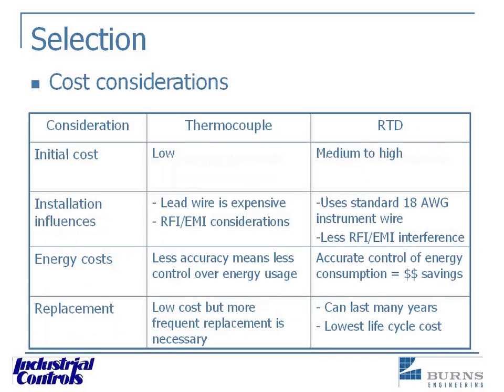Here are some cost considerations. And again, when your temperature demands a thermocouple, all well and good, that's your only choice. But it seems a lot of the time, people will call up and say, look, I just need something down and dirty. I just got to get this thing going. And they opt for a thermocouple when there should be other considerations. People are cutting corners. You're trying to save money. I understand that. But when you take a thermocouple and you add the thermocouple run wire back to it and the longevity of the thermocouple, I guess what I'm saying is you really need to keep an open mind before you choose a thermocouple over an RTD if it's just coming down to cost.